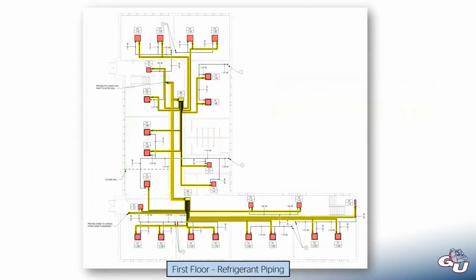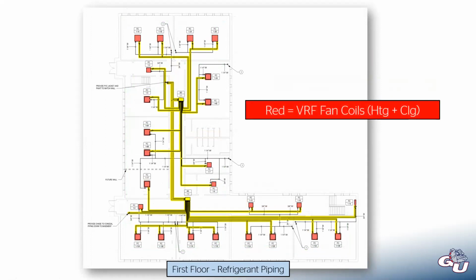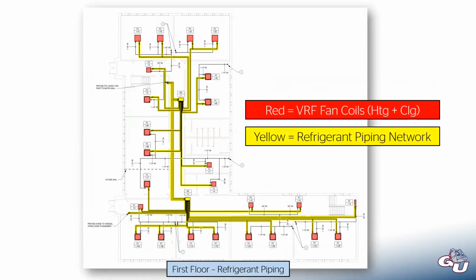On the refrigerant piping side, we usually show these on different floor plans because otherwise it gets very messy with our drawings. This is still showing the fan coils in red, so our heating and cooling units. And then in yellow, that is our refrigerant piping network. This is only one floor. This isn't showing the floor below. Right here, that's where the piping goes down to the first floor, and then it eventually goes outside to those heat pumps somewhere over here.